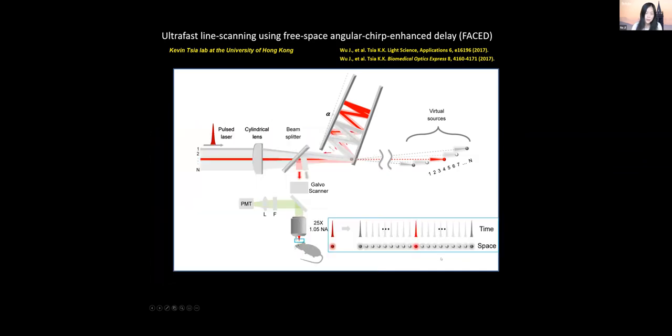Here, the lantern is one laser focal point, and the mirror pair generates an array of sub-pulses that are spatially separated and scanning the sample in one dimension, but also temporally delayed so that we can separate the fluorescent signal excited by those individual foci. In other words, we do not need to scan the laser along a single dimension to form an image, we just need to use an orthogonal galvo to scan it in the orthogonal direction.